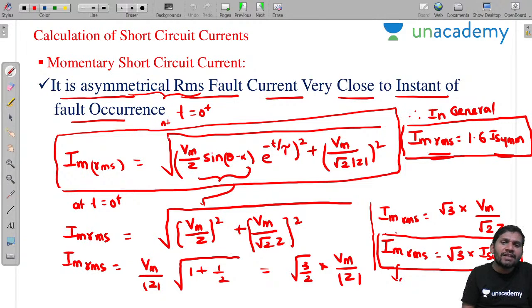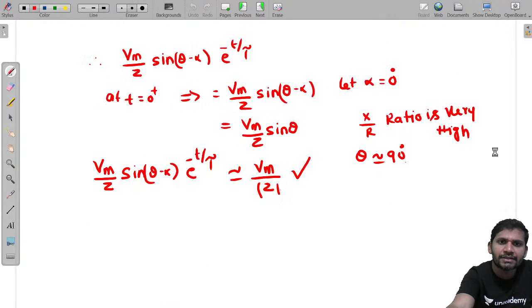This is the momentary RMS current, the momentary short circuit current, measured as an RMS value. This is a very important consideration in circuit breaker selection; circuit breaker ratings are also specified in terms of momentary current. Im RMS equals 1.6 times the symmetrical current. Actually the theoretical value is 1.73, but here I've done an approximate analysis, so practically you take 1.6 times the symmetrical current.